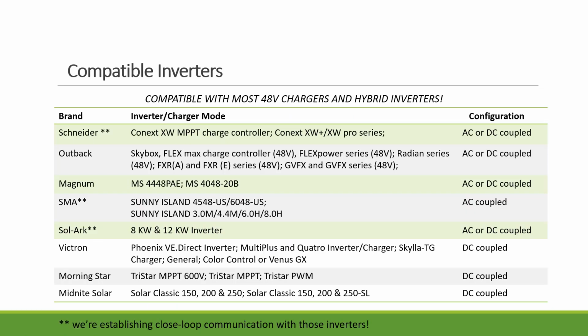Here's a list of inverters that we'll work with. A lot of well-known brands that have also been in the energy storage market for a while, like Schneider, Outback, Magnum, SMA, Victron. We are a Schneider Outback approved battery partner. We are on Schneider's literature. We also have integration guidance with all of those inverters, available on our homepage. We are currently establishing closed loop communication with those inverters. Again, it does take a little bit of time because, while every integration itself is easy, all those manufacturers have their own priorities, especially with Rule 21, phase 1, phase 2, phase 3, which really keep them very busy.